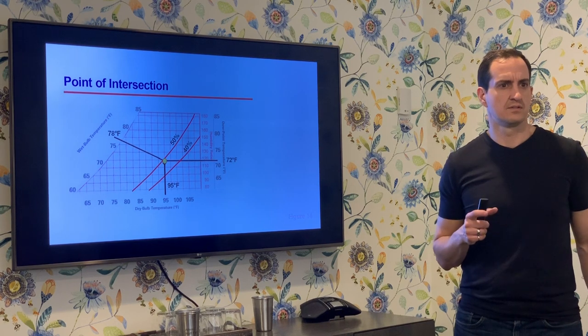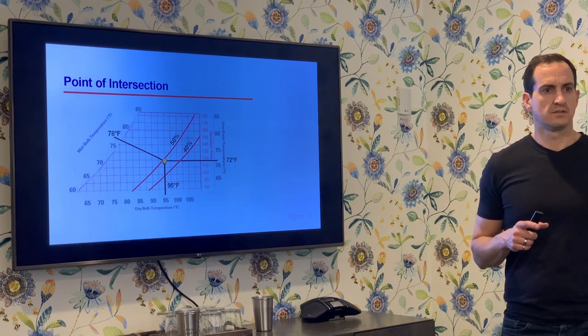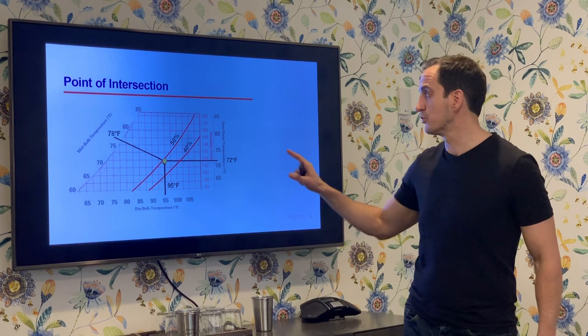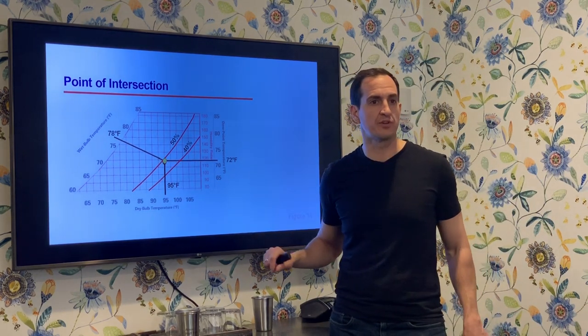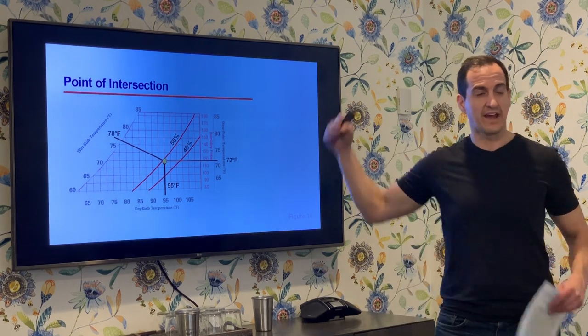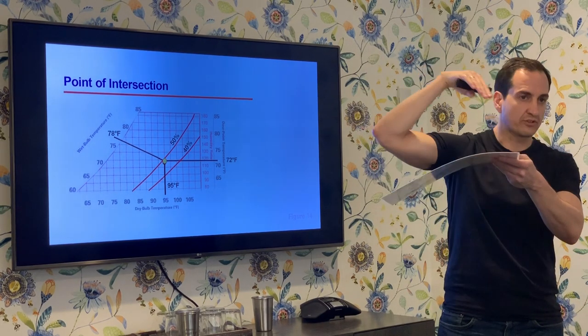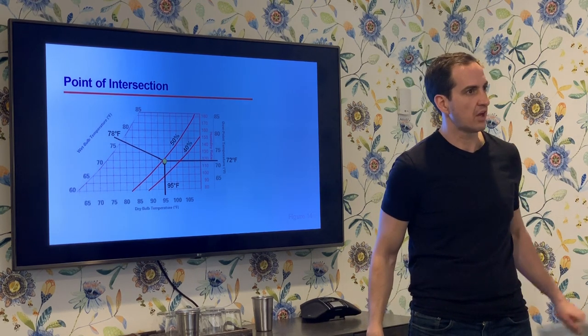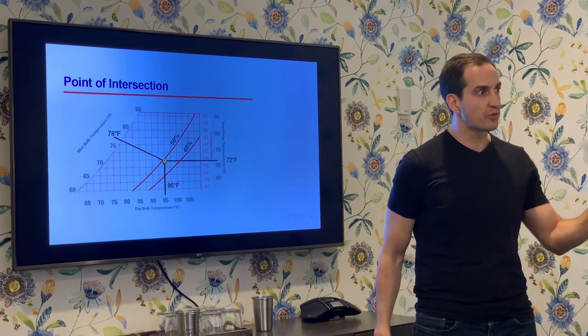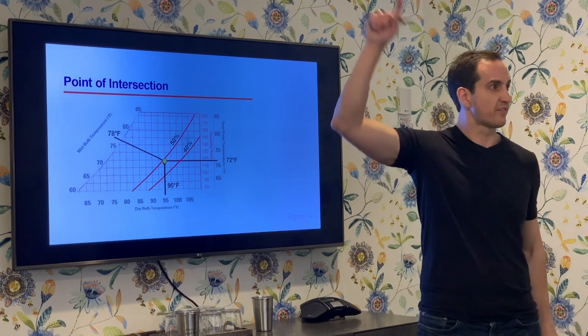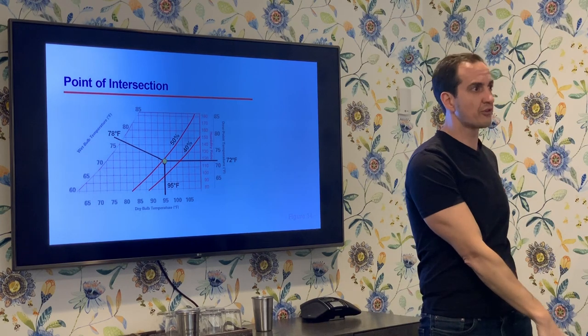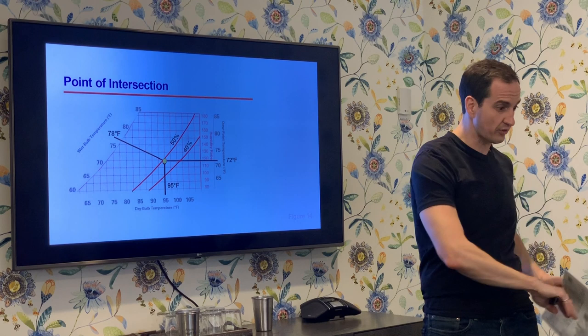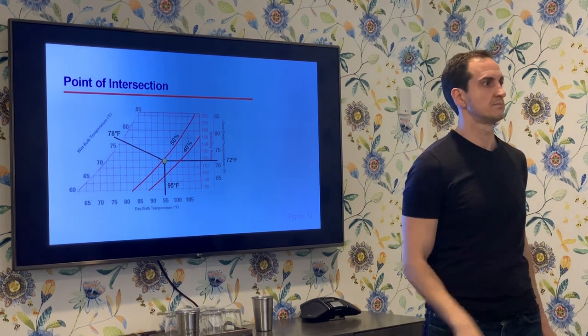At 72°F, if we take the same air and drop it to 72°F, anything below that and water will start condensing out of the air. If we take any surface below 72°F into 95°F air at 48% relative humidity, water is going to condense on anything 72°F and below — as the air hits that surface and gets closer and closer to that temperature, that is where moisture will condense. What happens at night when the temperature drops? The radiative effect of losing energy into space cools metallic surfaces on your car below the dew point — that's the dew on your car.